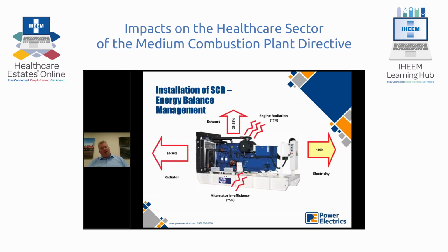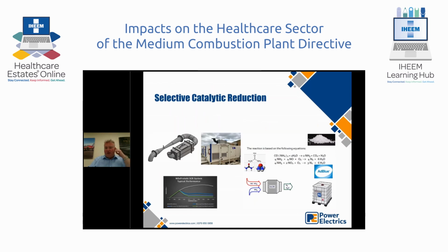So a little bit of a conversation about installing SCR systems. This is the generic FG Wilson generator system on a skid, an open unit. What it's really illustrating is that the engine is around 40% efficient with electricity, so you lose roughly 60% through the radiator and exhaust combination. Bearing in mind the SCR is fitted on this exhaust, some of the heat coming out is in excess of 400 to 500 degrees, which is fine because you need that for the catalyst to work. For every kilowatt of power you produce, you generate 2 kilowatts of heat as a rough rule of thumb. So you need to allow for that heat whenever you install generators into any installation.